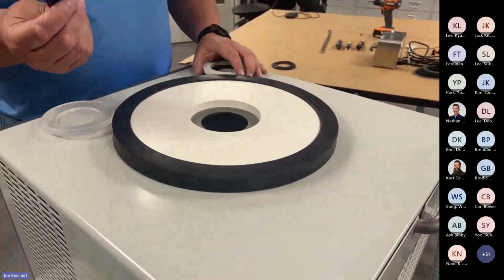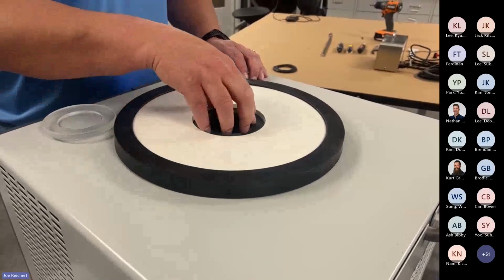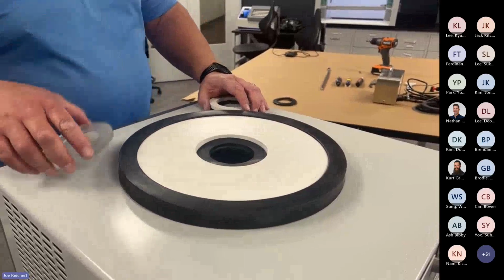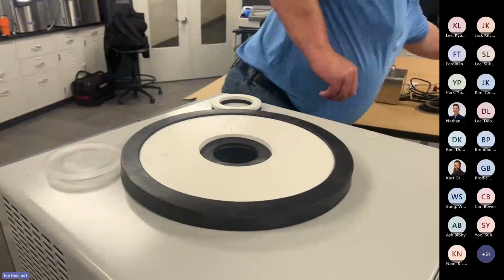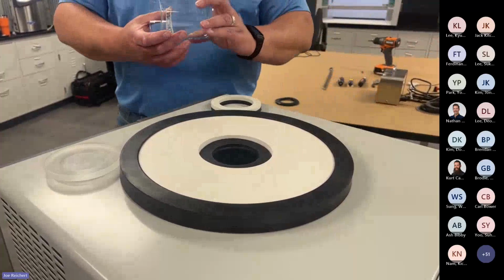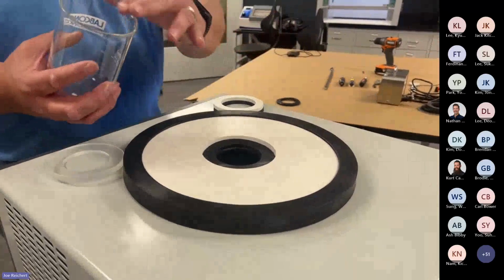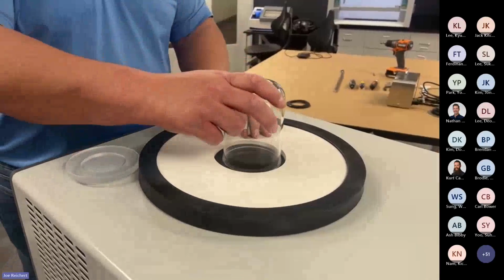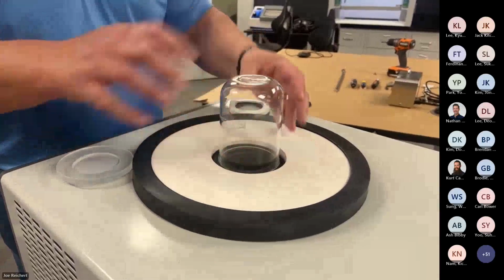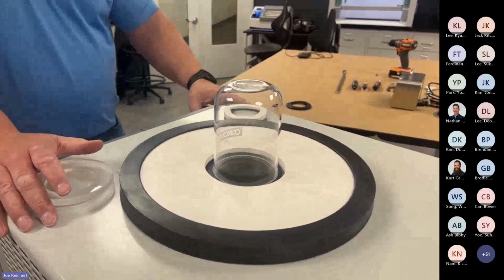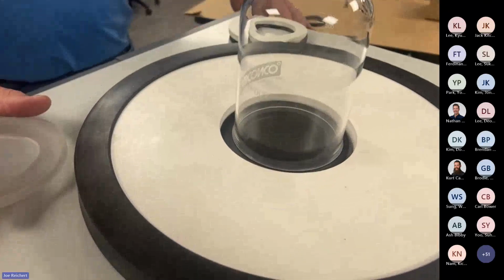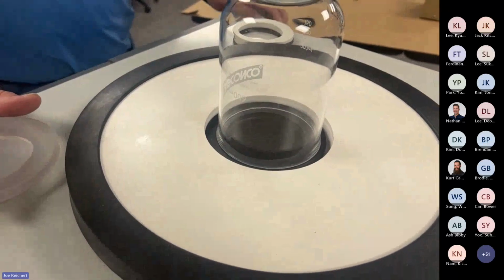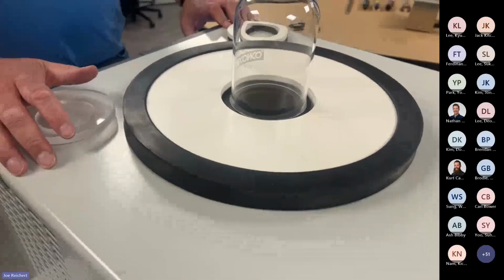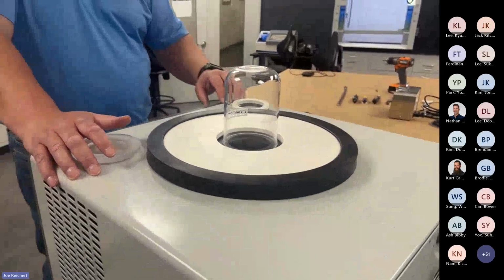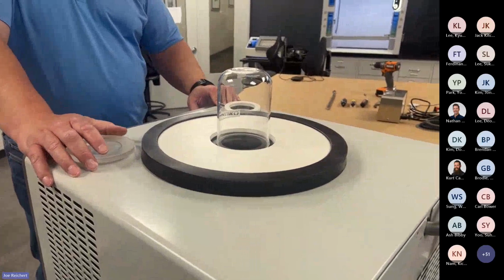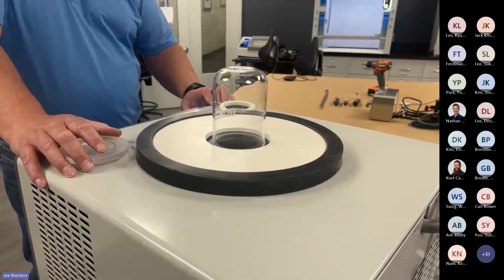For this type of testing, you really only have to have one gasket if you want to. You can use the plug, or you could use a 600 ml freeze dry flask. These have a rim of the mouth that's big enough to fit right on top of that gasket. And with this type of test, you do want the cooling on, since you are going to be pulling vapor across a coil. So you have room vapor in the room that could get in your pump. Won't be much, but it's always best to keep as much out of it as you can.